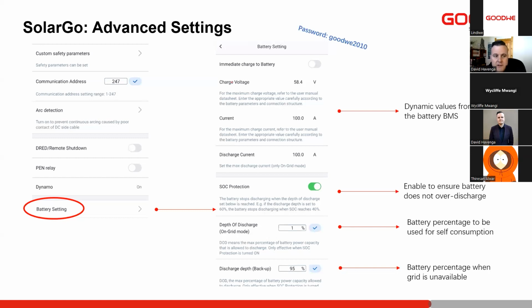Here you also see there's charge voltage, charge current, and discharge current. These values, the charge voltage, the charge current, discharge current, are all dynamic values from the battery BMS. And when we select our battery type, it will select some default values. But these values that are displayed here are all dynamic values from the battery BMS.